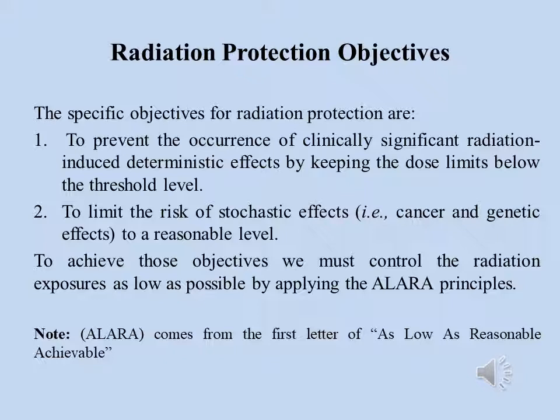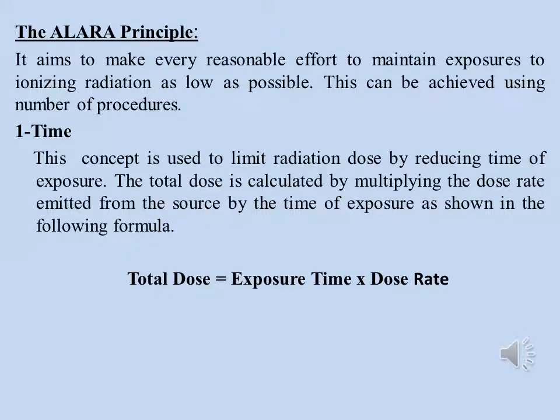To achieve those objectives we must control the radiation exposures as low as possible by applying the ALARA principles. Note, ALARA comes from the first letters of as low as reasonably achievable. The ALARA principle aims to make every reasonable effort to maintain exposures to ionizing radiation as low as possible. This can be achieved using a number of procedures.